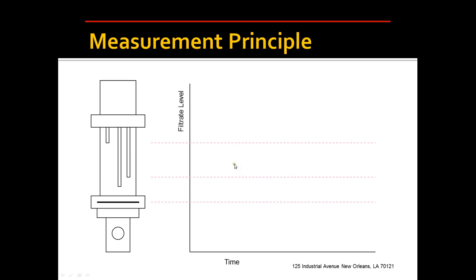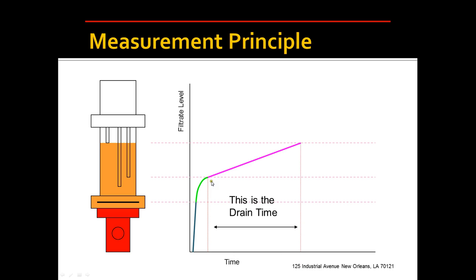Looking at it a slightly different way, if we were to graph the height of filtrate in the system as a function of time, this is what it would look like. At first, the stock would rise very rapidly because there's nothing to impede it. When it hits the screen and that pad starts to form, the response goes nonlinear. This nonlinearity is a function of a number of different things, mainly consistency, and that's part of the reason why we don't actually start the analysis there. What we have found is that after that pad has formed to some nominal thickness, the behavior linearizes. It's not a perfect line, but it's close enough that we can model it that way. And so the drain time measurement is basically the amount of time between this lower probe and the upper probe, and that is the native measurement of the Drainac.